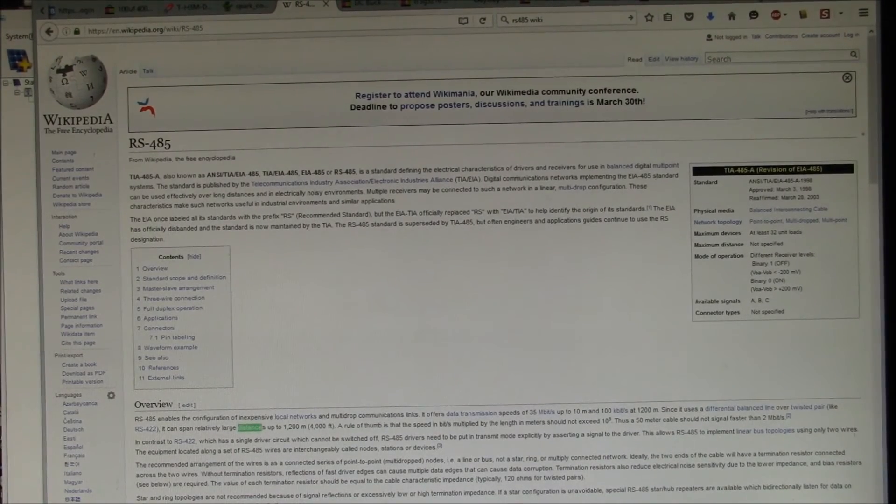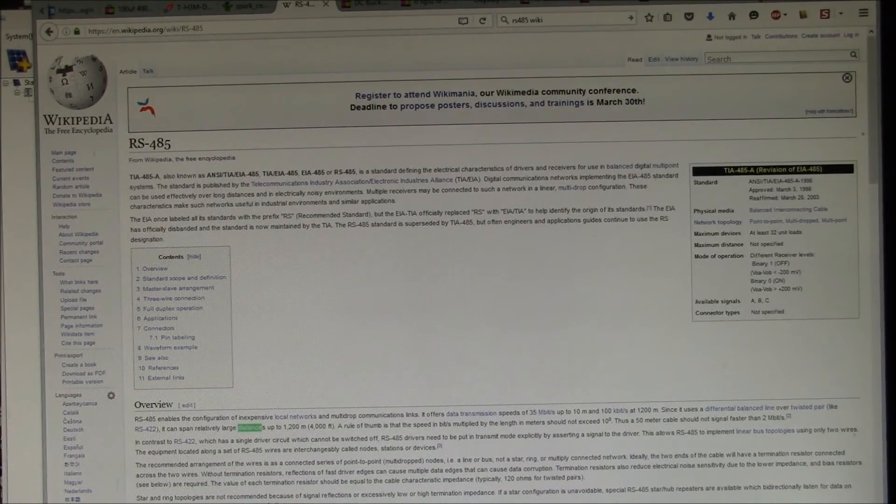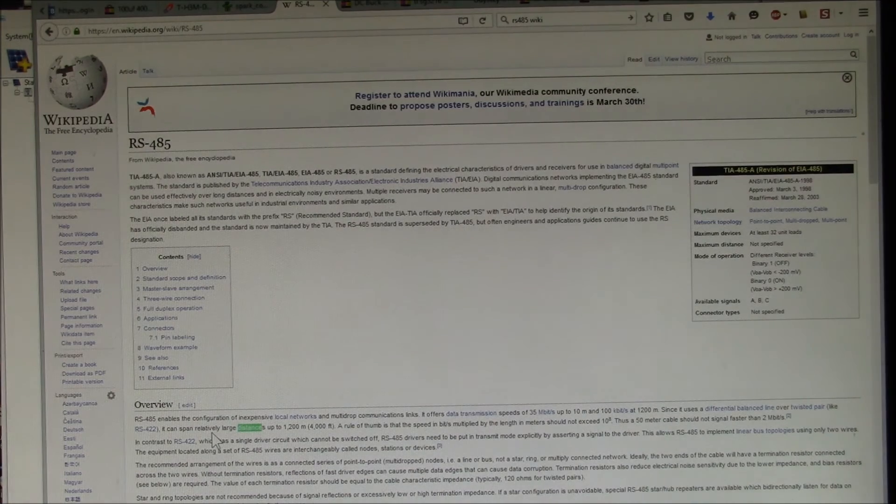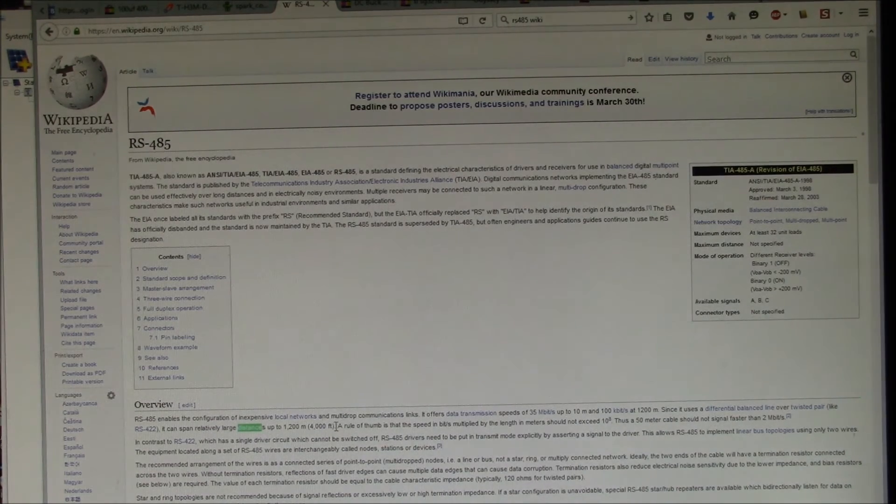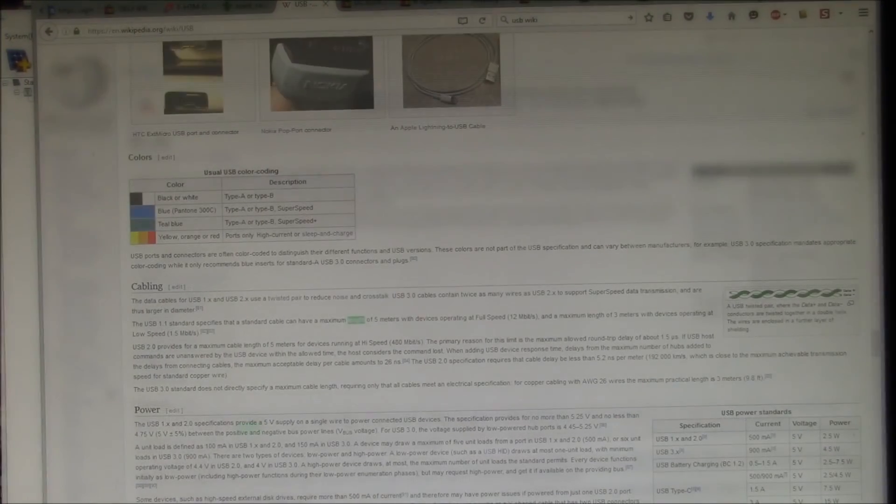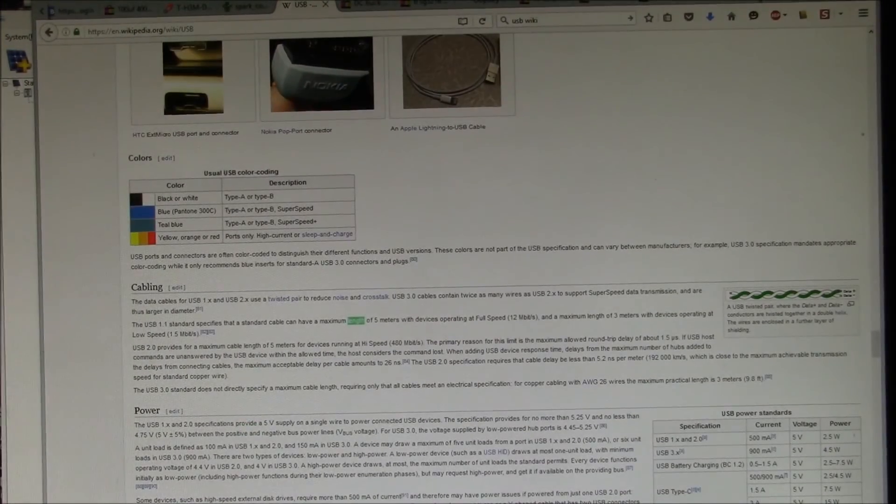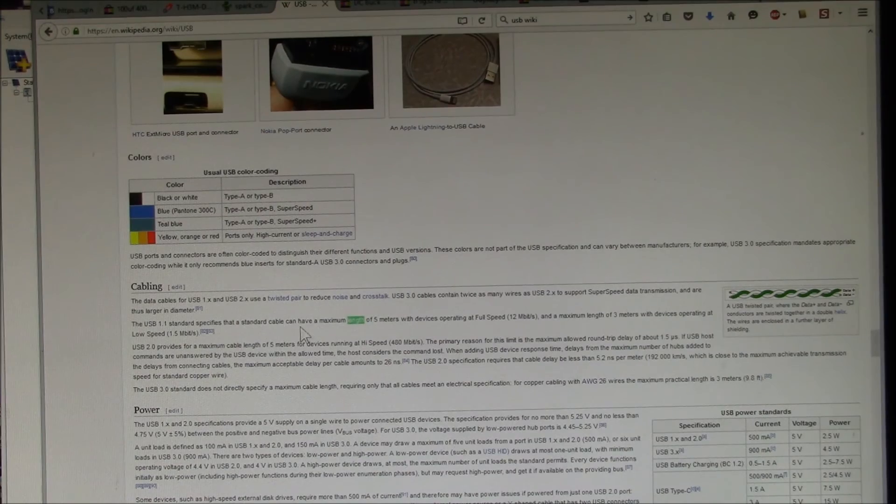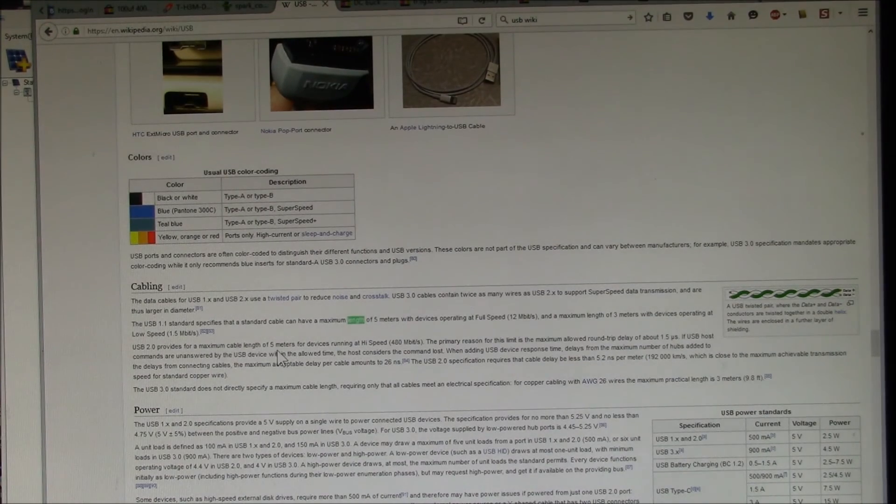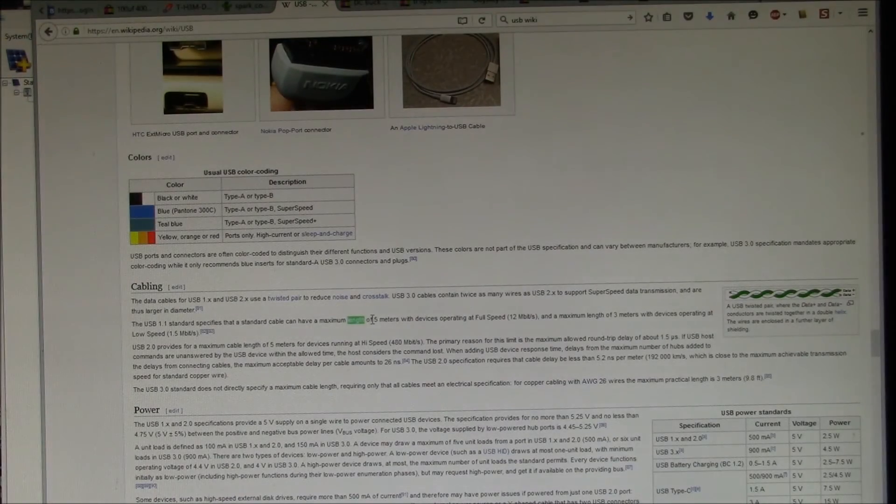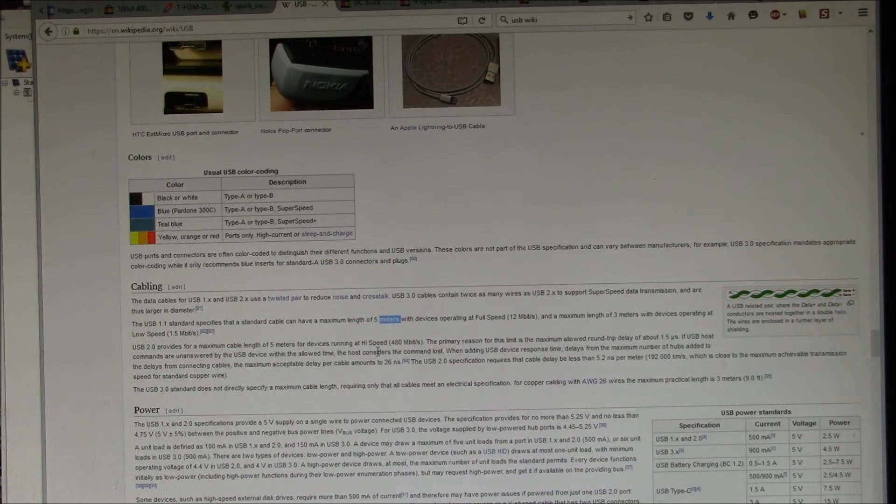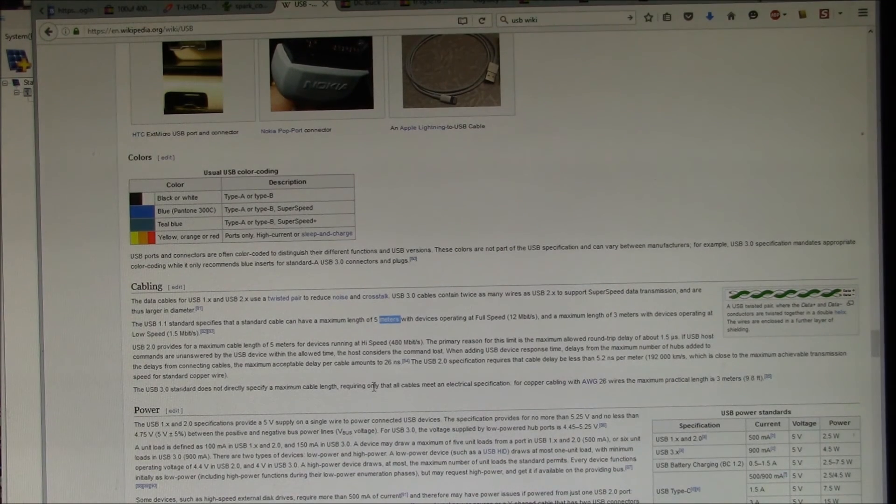Here's the RS-485 Wikipedia page. Like it mentions here, it can span relatively large distances up to 1,200 meters or 4,000 feet. If we look here you can see under cabling, USB 2 provides a maximum cable length of 5 meters. So 5 meters is the longest you can extend the USB end of the cable, but the RS-485 end you can extend that up to 1,200 meters.